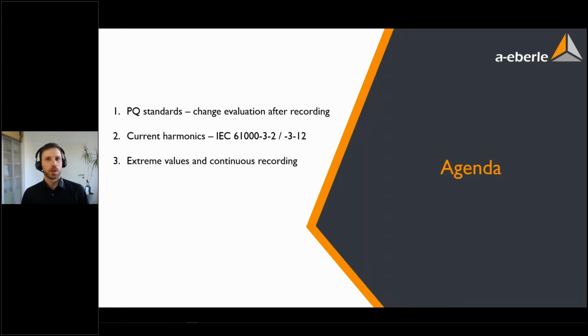Then I'm going to talk about extreme values and the continuous recording. So what does the 10-minute average value tell me compared to a peak value, for example, or a 10 millisecond or 200 millisecond extreme value? Later on, I will continue with harmonics, interharmonics, supraharmonics. So what's more or less the difference and what is the best way to evaluate them? There are different types of display within PQMobil, and I will show you that in detail.